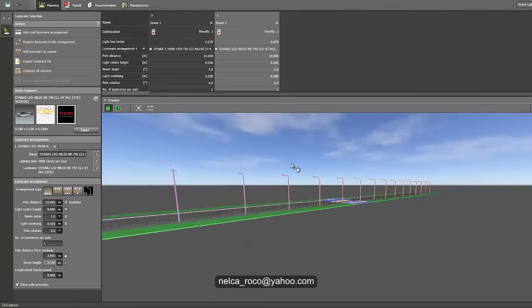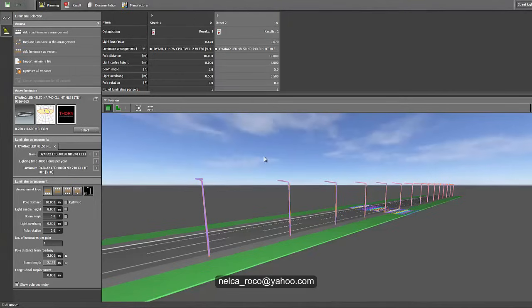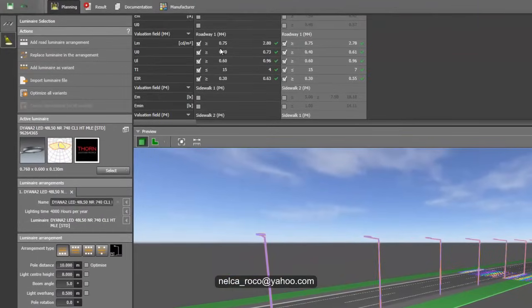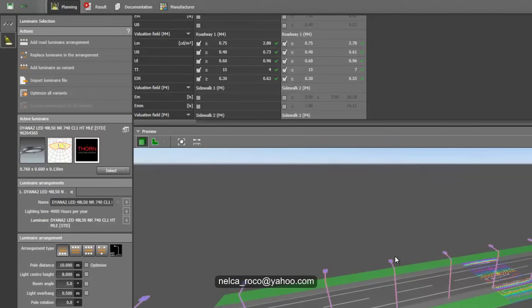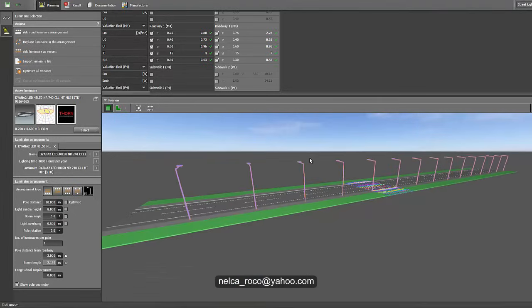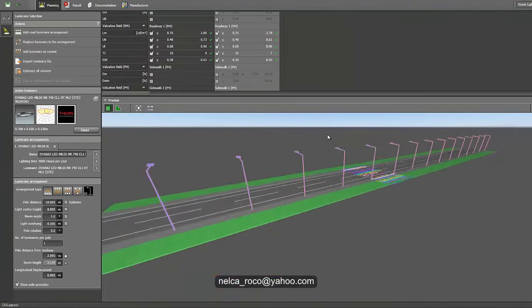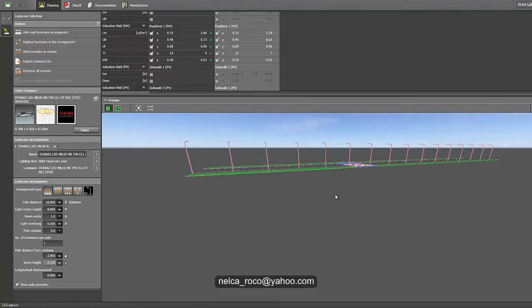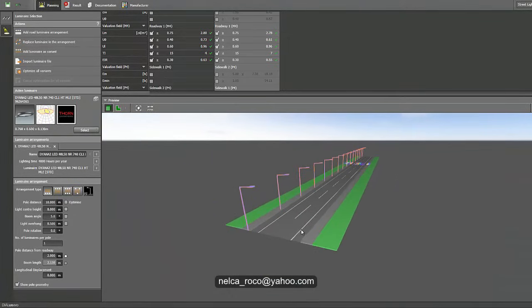The fitting has been changed. Let's run the calculation and check the results. Yes, it's also good — the candela distribution, everything looks nice. I think the 10-meter spacing makes it easy to achieve the lux value. Sometimes in road lighting if you really want to compete with other manufacturers, the first objective is to reduce the quantity of poles and luminaires by increasing the spacing. But he specified 10 meters, so we can only play with wattage and pole height.